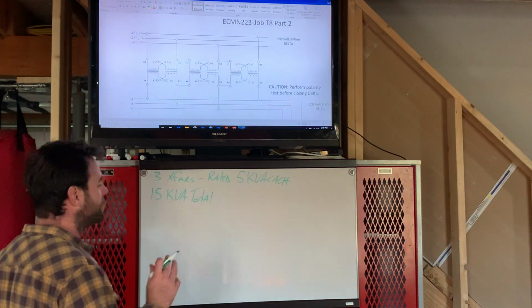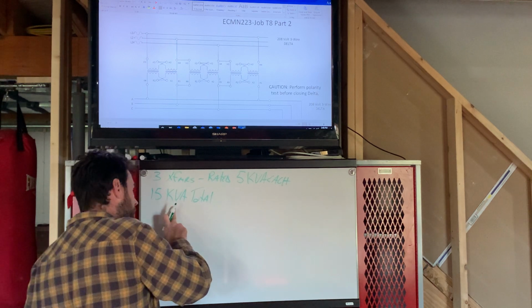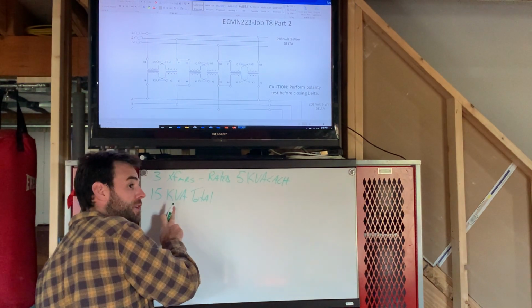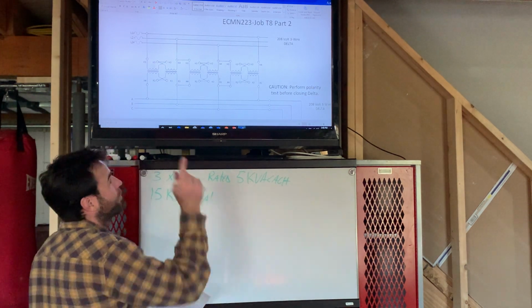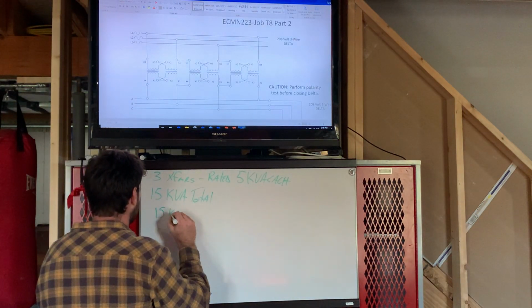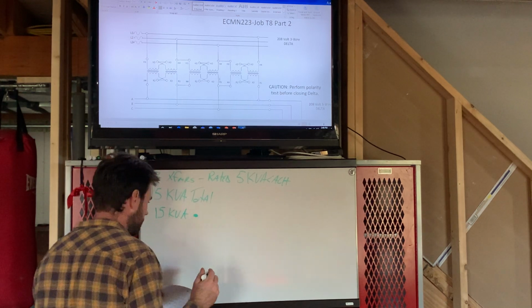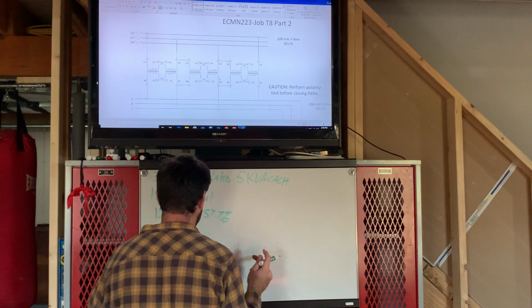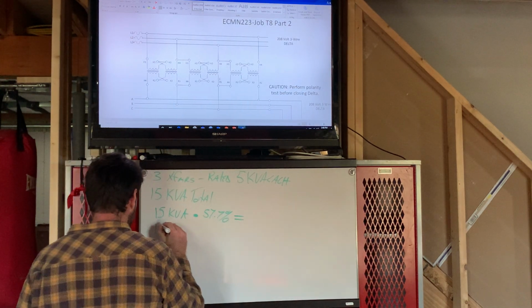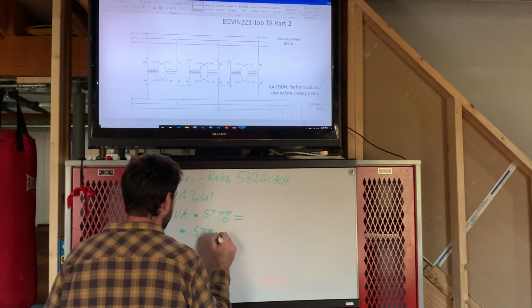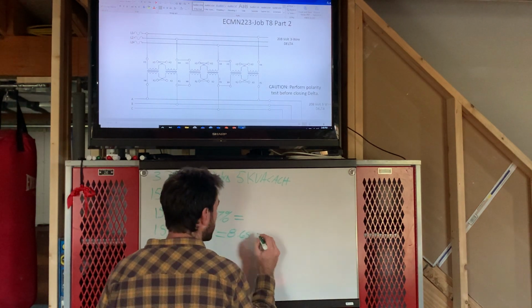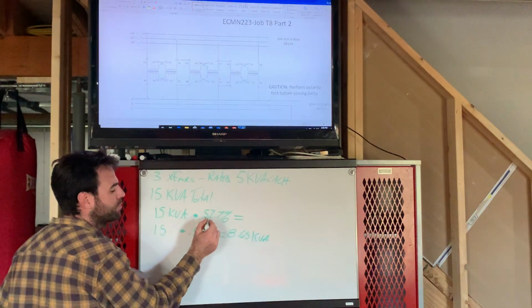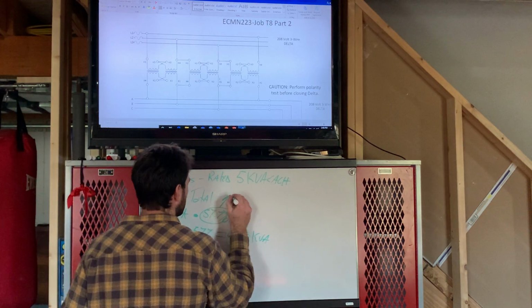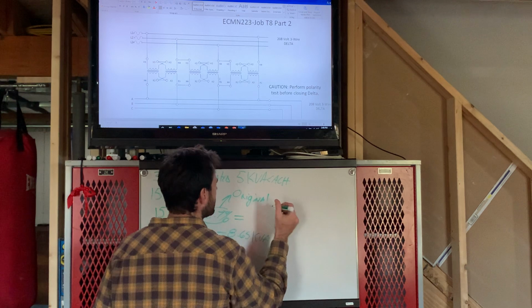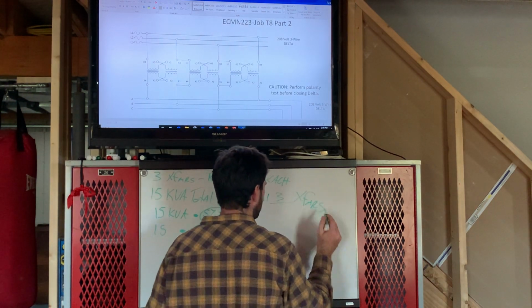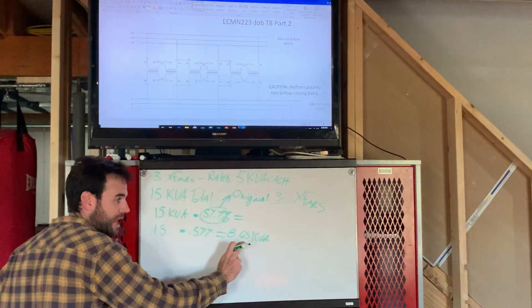So, what you could do is if you had the original transformer bank, so say 15 kVA, say you want to see what your kVA capacity was going to be if you were to lose one. So you lose a transformer, we're going to operate in an open delta with 2. You could take 15 kVA, because you knew that was the total, multiply that by 57.7%. That's going to come out to, or 15 times 0.577 equals 8.65, in our case, kVA. So, 57.7%, the original 3 transformers. That's what you're going to use, the 57.7%. You see, this comes out to 8.65.